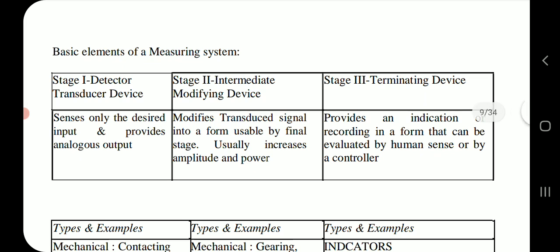Basic elements of a measuring system: Stage 1, detector transducer device. Stage 2, intermediate modifying device. Stage 3, terminating device. Senses only the desired input and provides analogous output. Modifies transduced signal into a form usable by the final stage. Usually increases amplitude and power. Provides an indication or recording in a form that can be evaluated by human sense or by a controller.